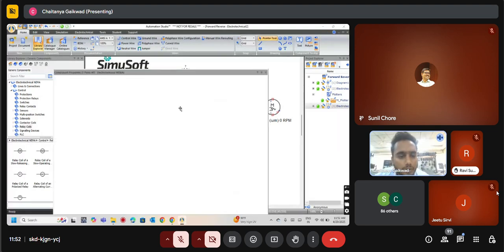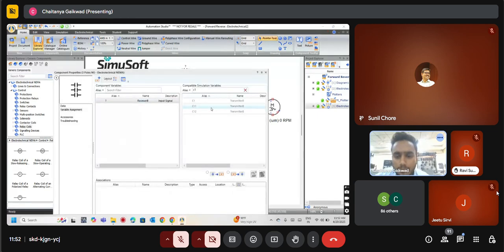So the naming I have used over here is as per our convention. So I have connected this contactor, I link my this contact to C11. So now we can see the blue lines, blue contacts on both my relay coil and my contactor. So whenever this coil gets energized, my contactor will get closed and allow the supply.